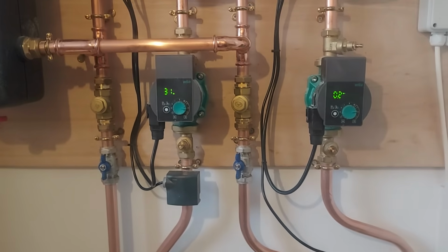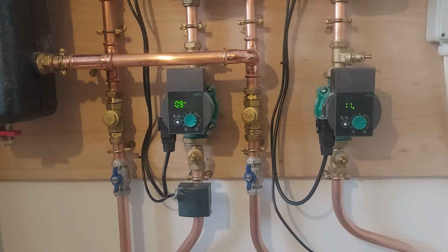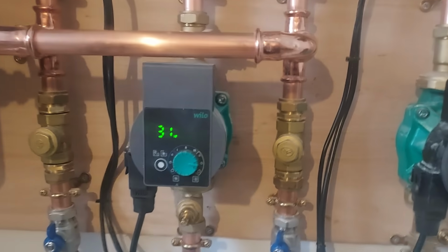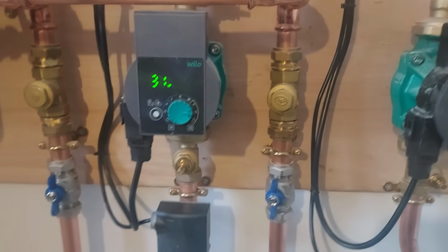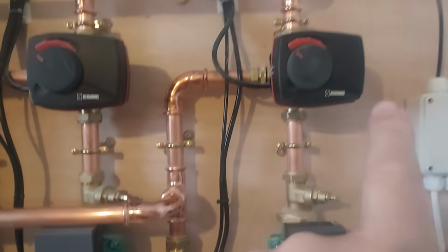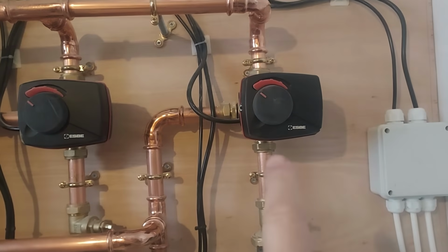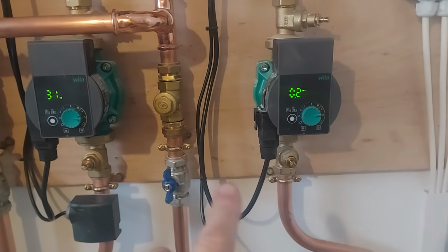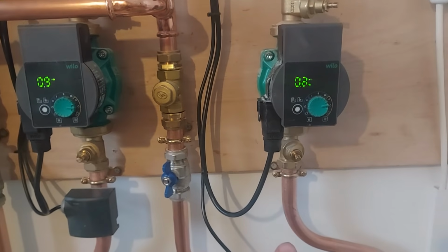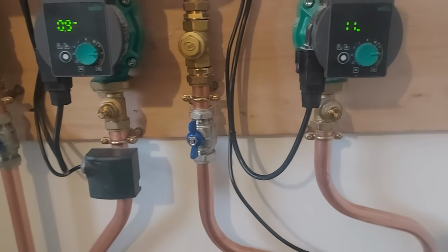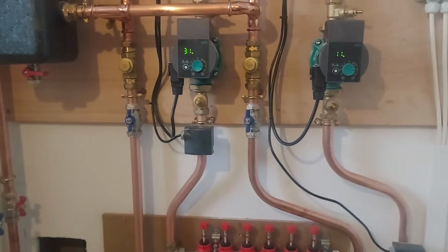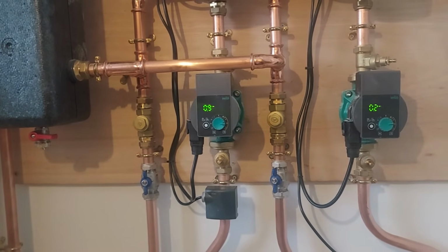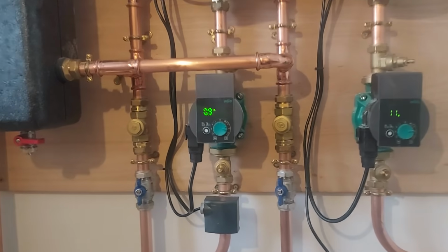Now this one, interestingly enough, has the non-return valves on the circuit side, and I'm interested to see if this gives a problem. I know somebody else on the forum recently did the same, and found that when the system went into cool down, these mixing valves locked closed, and there's such a good seal on them that it seals this circuit completely, and that's with hot water. So as that water cools down, we get a negative pressure, and you get quite a drop on there. Now also we're trying to find out why we need the non-return valves in the first place. So if anyone's got any ideas, please let us know.